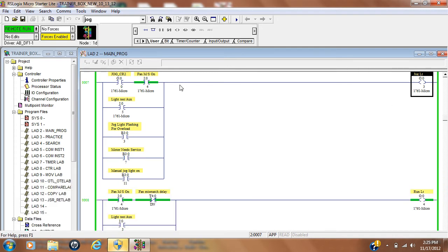And if you look at this rung, there are several branches to this rung. And you'll see this first branch, it has one bit on, but not this bit. So that's not what's causing it to flash. You go on down the line, and you'll see this highlighted bit. When it's highlighted, that tells you it's true. And as you can see, when this goes true, our OTE goes true. And by the way, in Logix 500, you'll see this description here. It's O3. O means it's a real world output, and that's my light flashing.